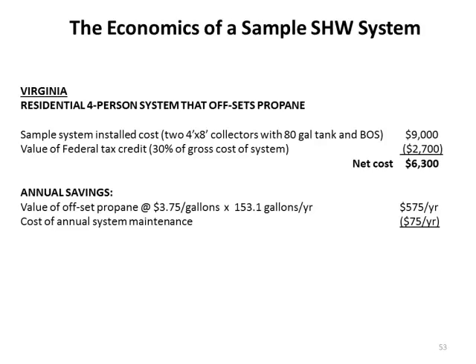Certainly after about 5 years on glycol-based systems, the antifreeze should be replaced. And maybe after 10 years, a pump will go bad or the controller or something like that. But these systems, again, if they're designed and installed correctly, they should last and be maintenance-free for their full 25-year life, except for just regular wearing out of parts. So $75 per year for maintenance. We do the math. We come out with a savings of $500 per year.